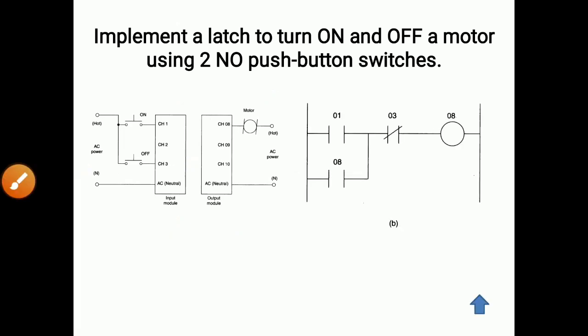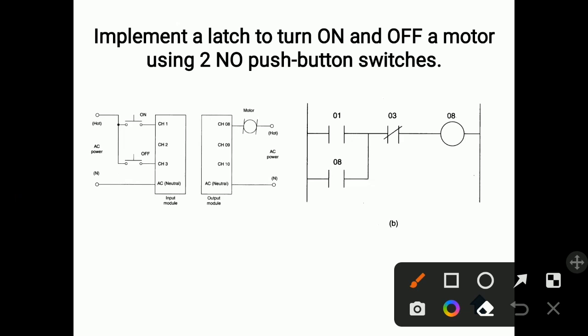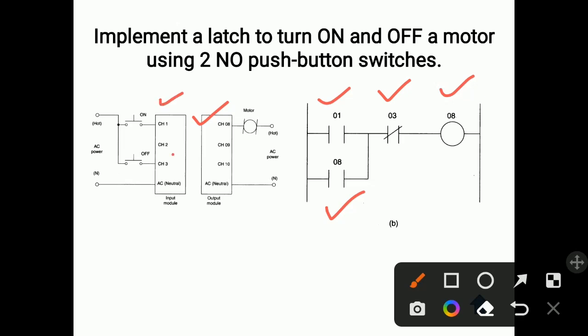This is the actual ladder diagram for this operation. Here zero eight means motor, because channel number zero eight is the motor. The same contact for this motor coil is taken here as zero eight. Zero one is the normally open input switch and zero three is the normally closed switch — channel number one and channel number three switches are shown here. You can think of zero eight as motor or as the coil of the motor.